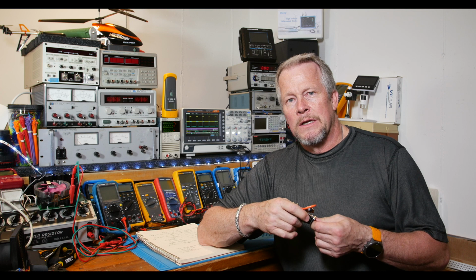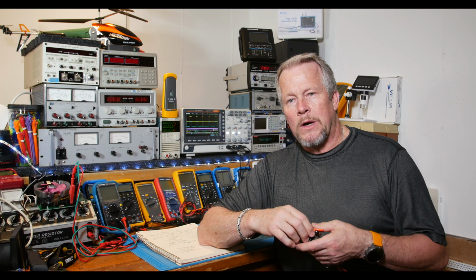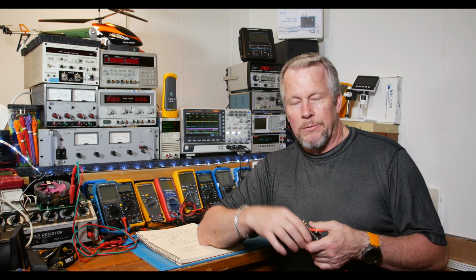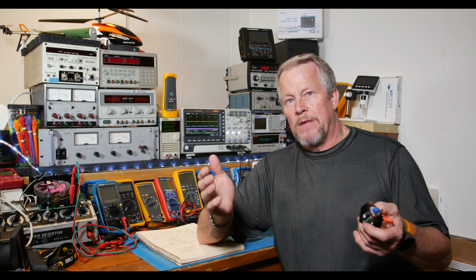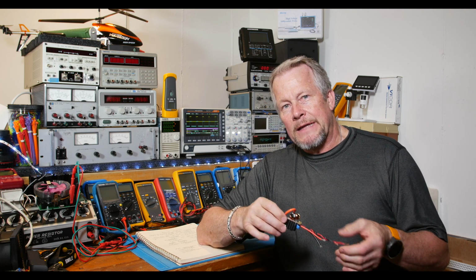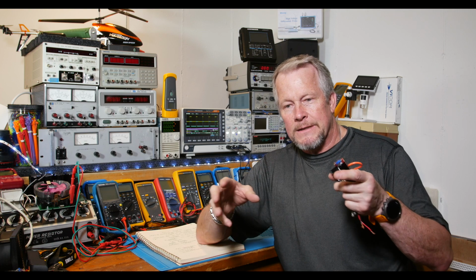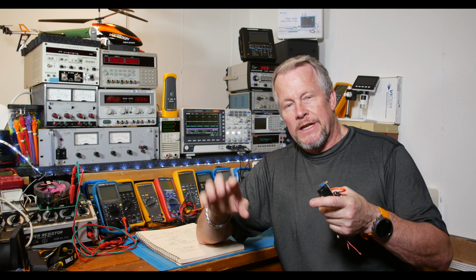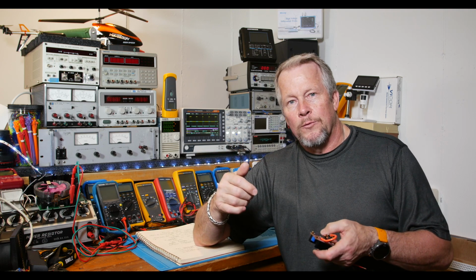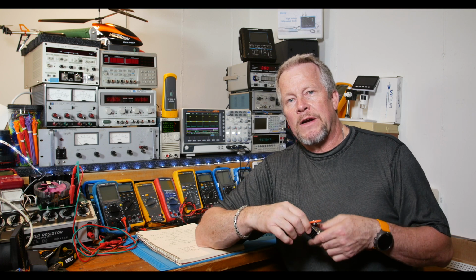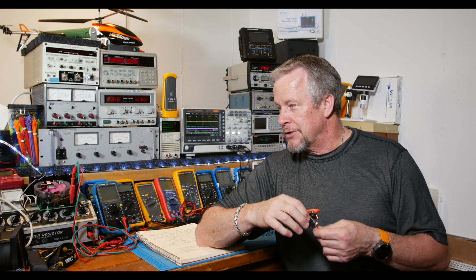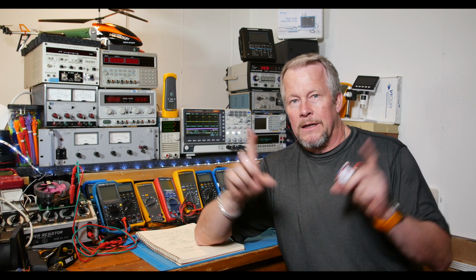And so with an AC power supply, if you need good power factor control, good quiet, low harmonic distortion kind of requirements, you can use a multi-phase transformer. That's where you can bring three-phase in and come out with 9-phase, 12-phase, or 15-phase. It's really an interesting way they do that. They take the different phases and wind the transformer such that you get these other phases. It's really cool how that's done. When you do that, you get good clean power factor and very low harmonic distortion. So that's another way to do it in a linear fashion.